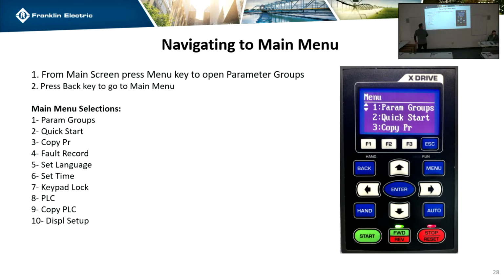Okay, so from the main menu, you have the parameter groups, quick start, copy parameters, fault record. You can change the language, set the time. This has a real-time clock in it. When you're using Bluetooth, it will use your phone to sync the clock. If you're not doing that, you just go in and set the time. You can lock the keypad out with a pin. If you forget the pin and you call us to unlock it, the drive will be reset to factory defaults. You'll have to reprogram the whole thing, but it can be done.